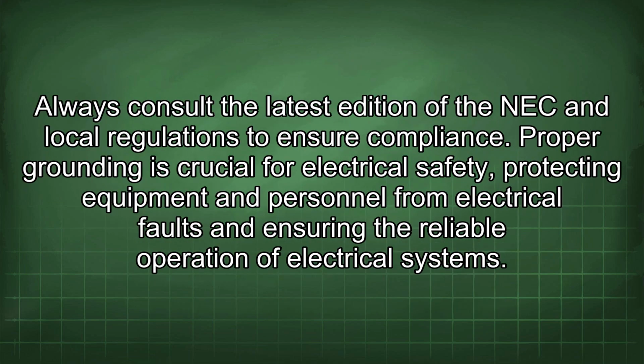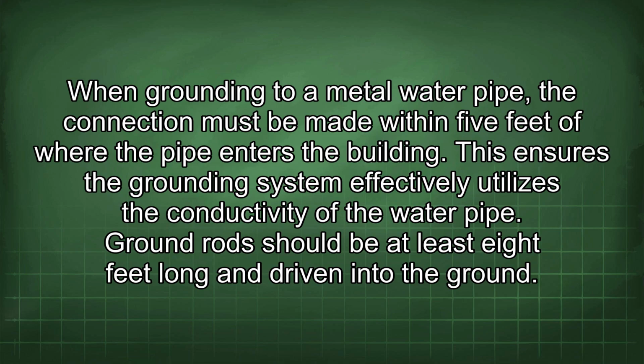Always consult the latest edition of the NEC and local regulations to ensure compliance. Proper grounding is crucial for electrical safety, protecting equipment and personnel from electrical faults and ensuring the reliable operation of electrical systems. When grounding to a metal water pipe, the connection must be made within 5 feet of where the pipe enters the building. This ensures the grounding system effectively utilizes the conductivity of the water pipe.